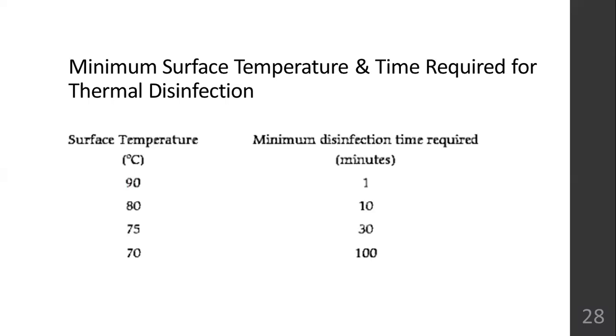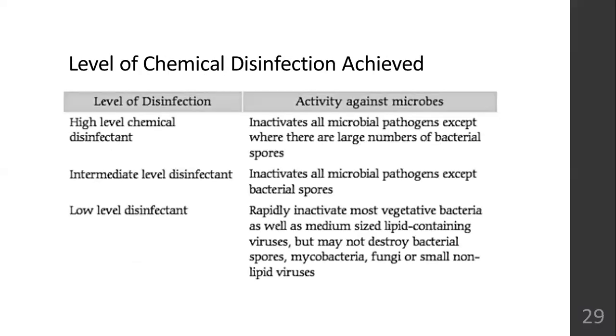So higher the temperature, lower the time required for disinfection. Okay. Higher the temperature, lower the time required for disinfection. You can see it from the table. When the temperature is high, the time required for disinfection is low. If 90 degrees Celsius is the temperature of the water or detergent water, 1 minute is the time required to do the disinfection. Okay. If 70 degrees Celsius is the temperature of the detergent water, 100 minutes, okay, so that is approximately around 2 hours, is used for disinfection.